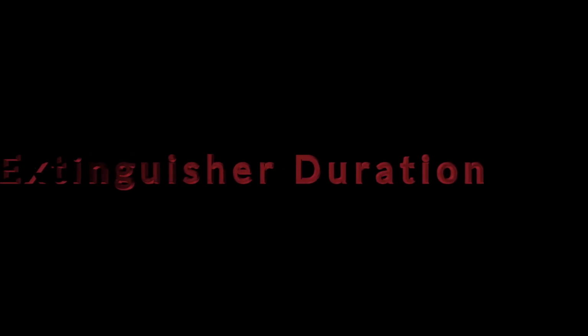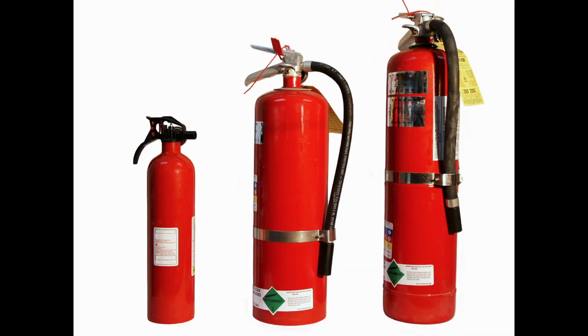A common misconception about fire extinguishers concerns their duration. The length of time a fire extinguisher lasts depends on its size. For instance, a 2.5-pound extinguisher typically lasts for 7 seconds, a 5-pound extinguisher for about 14 seconds, and a 10-pound extinguisher for between 22 and 26 seconds.